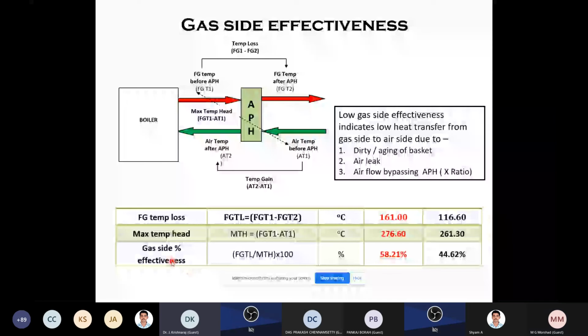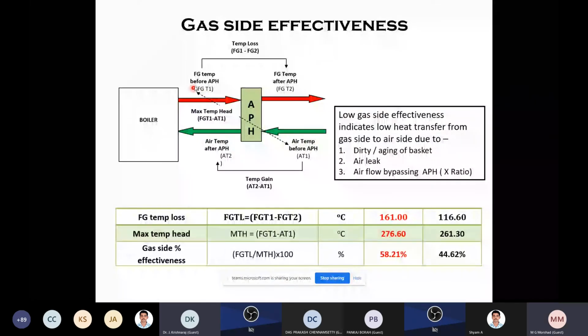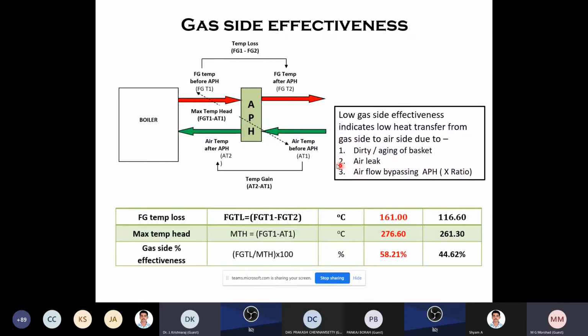First, the gas side effectiveness. I tell you, the total heat head is the flue gas temperature before and the air temperature before the air preheater. Because flue gas will be going this way. So flue gas inlet temperature minus air inlet temperature, the difference between the two is called the heat head. I perform this for checking the performance. The flue gas will be losing temperature here and the air will be gaining. So the flue gas temperature loss divided by the heat head gives the gas side effectiveness. Similarly, the air temperature gain divided by the heat head is the air side effectiveness. So these are the things we are calculating.